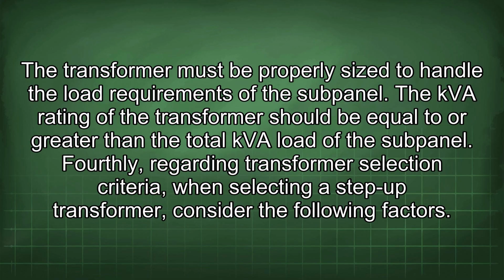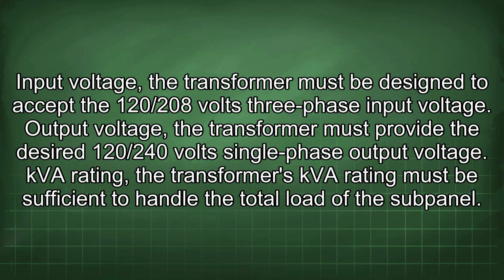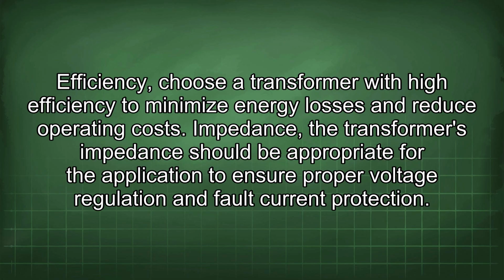Fourthly, regarding transformer selection criteria, when selecting a step-up transformer, consider the following factors. Input voltage. The transformer must be designed to accept the 120/208 volts three-phase input voltage. Output voltage. The transformer must provide the desired 120/240 volts single-phase output voltage. kVA rating. The transformer's kVA rating must be sufficient to handle the total load of the subpanel. Efficiency. Choose a transformer with high efficiency to minimize energy losses and reduce operating costs. Impedance. The transformer's impedance should be appropriate for the application to ensure proper voltage regulation and fault current protection.